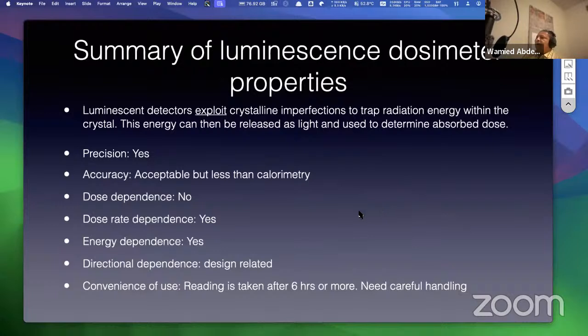Obviously, we cannot immediately give the dose to, let's say, a physician asking what the dose is based on TLDs. We need to wait for some time. So that's a disadvantage, but they're good if you want to monitor the dose received for radiation protection. This is a good dosimeter because it keeps the dose. We read it after 3 months, and that's it.